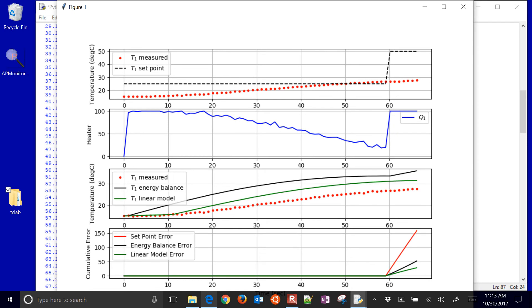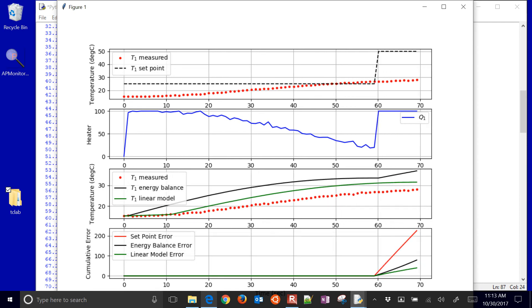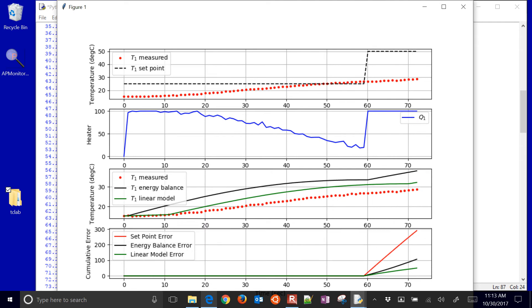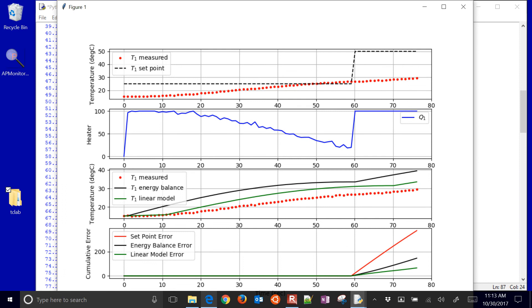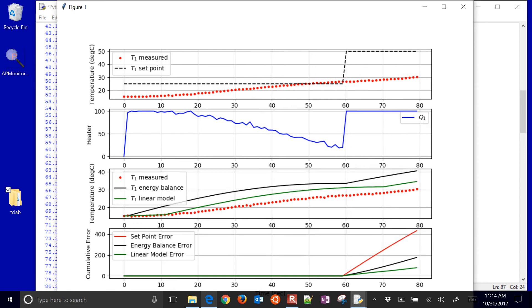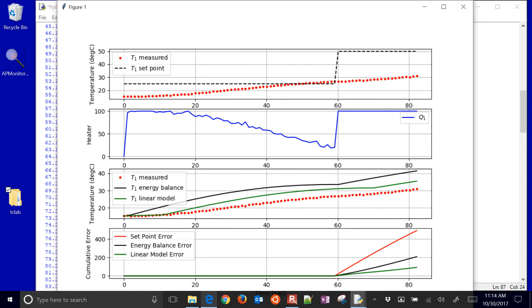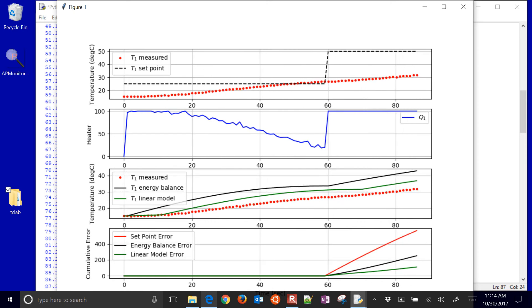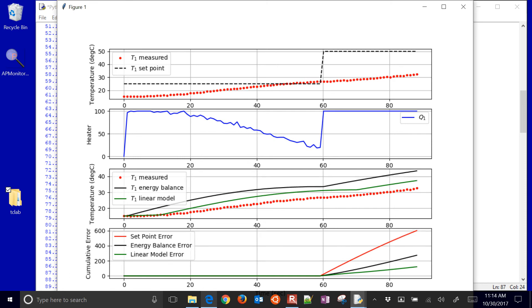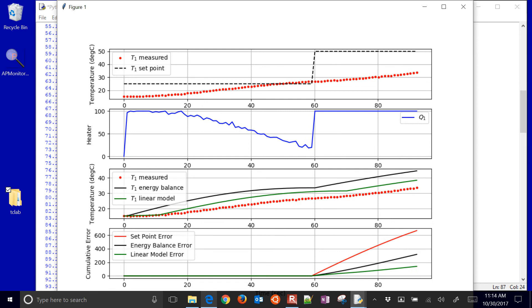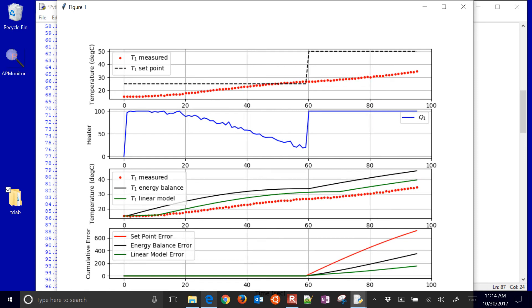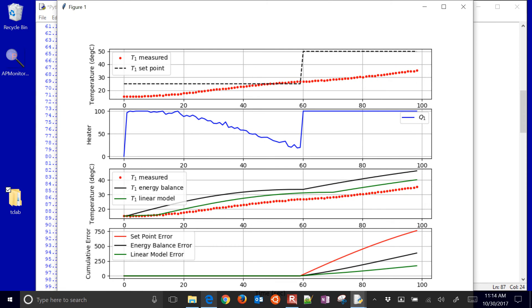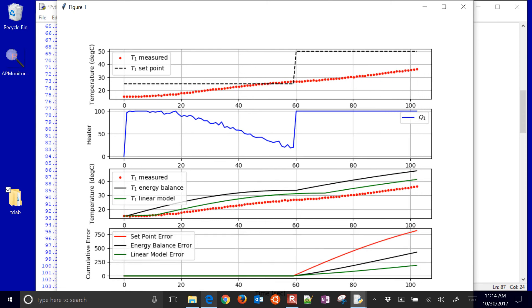And you can see the cumulative error start to rise. So at every second, every time point, it's taking the absolute difference between the measured and modeled values and adding that to the cumulative energy balance error and the linear model error. And then it's also looking at the difference between the set point and the measured value and accumulating that as well. So I'm adding to my cumulative error right now about 15 every cycle. And as you see, as it approaches the new set point, then that will start to decrease.